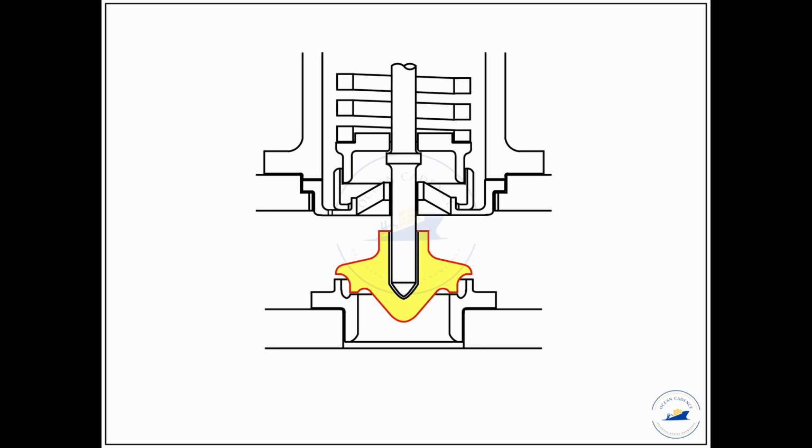Upon opening of the safety valve, you would often encounter the fact that this surface might be a little sluggish, a little brownish in appearance, and can have collection of mud or other rust formation. Hence, that has to be cleared specifically and very nicely before we carry out the inspection.